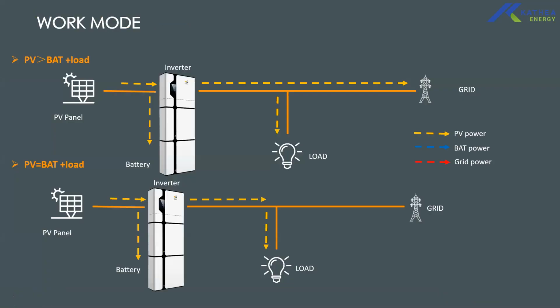So the work mode, when your PV is greater than your battery and load: as I've said, when the system receives PV, the first thing it supplies is your loads. After supplying your loads, it charges your battery. After it charges your battery, it feeds back to the grid. So when your PV is greater than battery and load, it will supply your load, your battery, and your grid. If PV is equal to the battery and load, that is a scenario where you're not feeding back to the grid. So the system would only supply your loads and charge your battery, and nothing will be fed back to the grid.